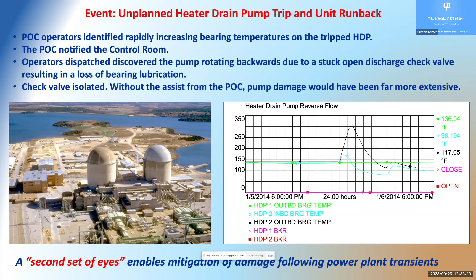But the POC convinced them to look, and they said, you're right. Why are the temperatures on this pump screaming up when it's offline? That shouldn't happen. They sent an operator out, and they found, as a result of the trip, a check valve that had stuck open, which was reverse flowing, making the pump spin backwards, and it isn't lubricated when it's reverse spinning. So they were able to isolate it and save catastrophic failure. So this is an example of how remote monitoring technologies, miles and miles away, can make a contribution, even at a nuclear power plant, during reactor transient conditions.